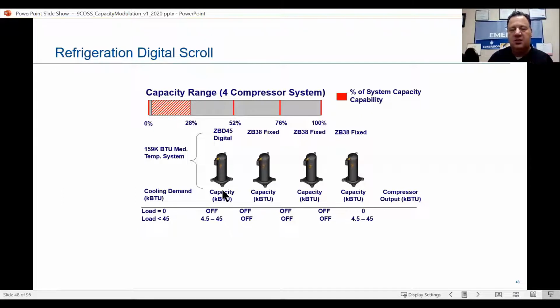It won't come on until it calls for at least 10% of its capacity. So at ZBD 45, 10% is going to be 4.5, 100% is going to be 45, okay? So we're calling for it at 10% on startup, the digital. So 10%, it's on, off. Now we go up to 52%. See the graph up here, all right?